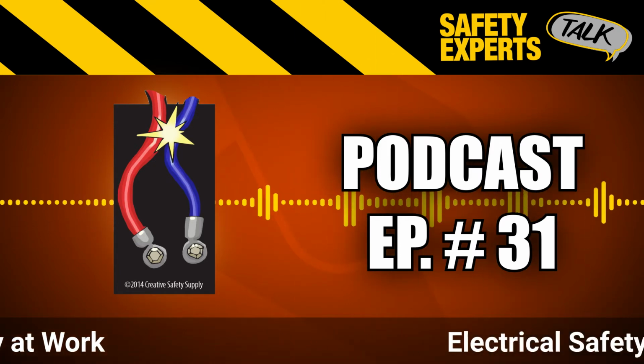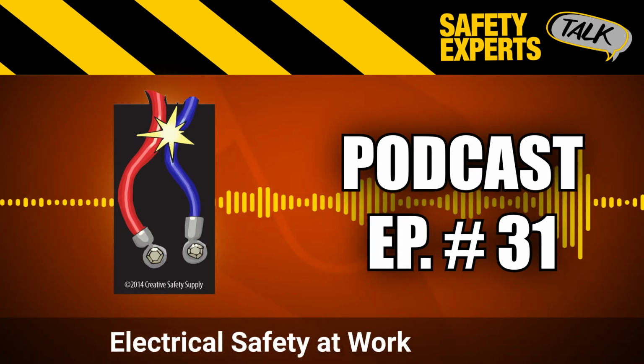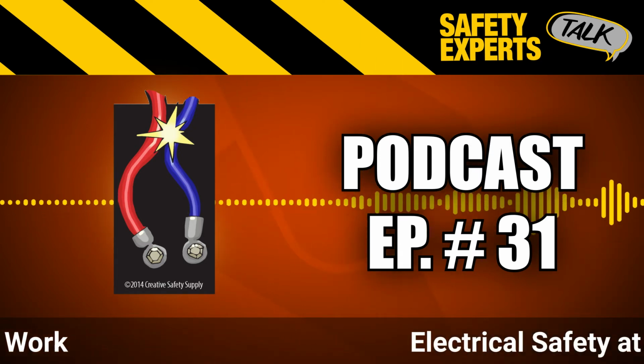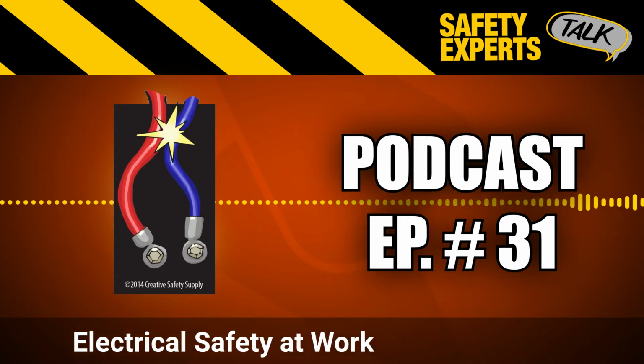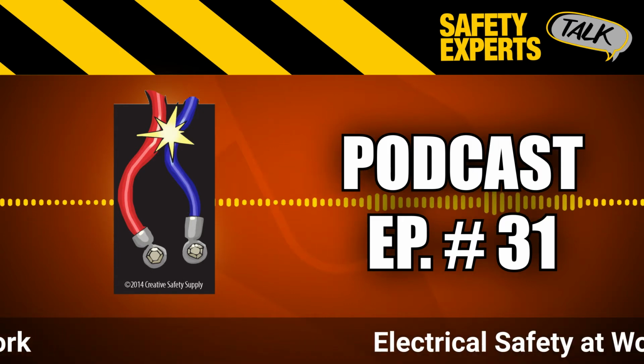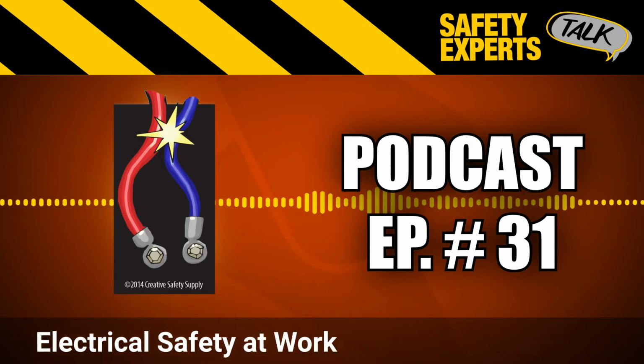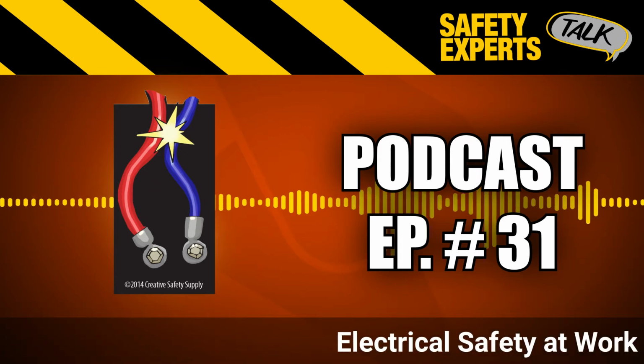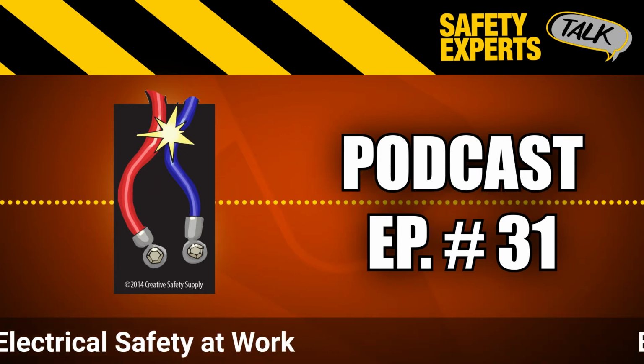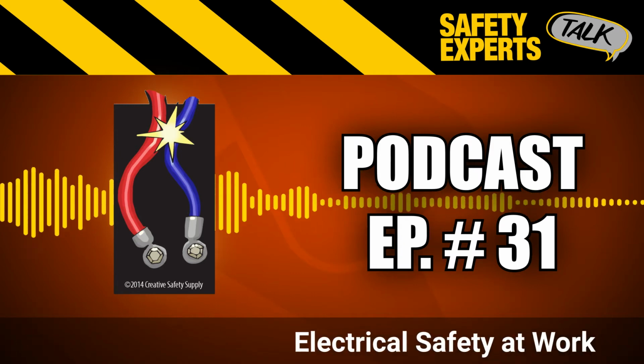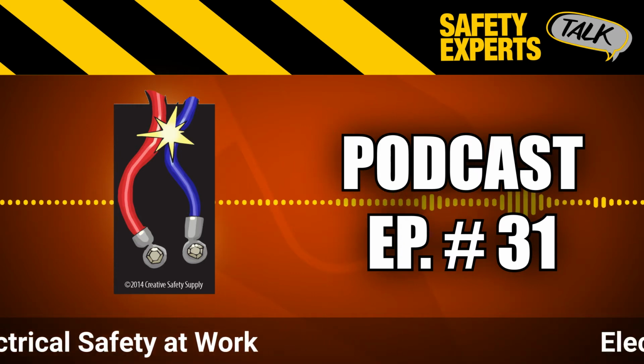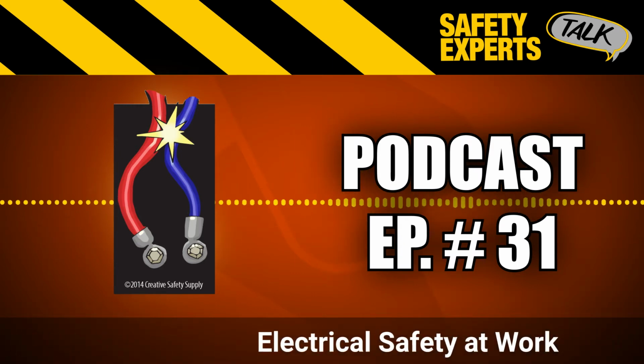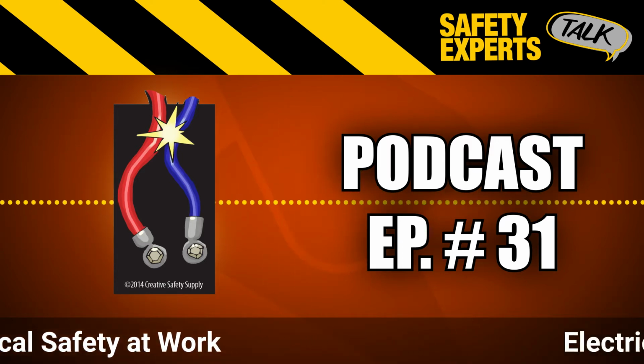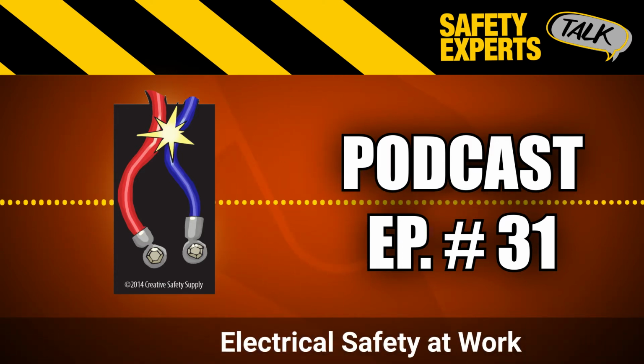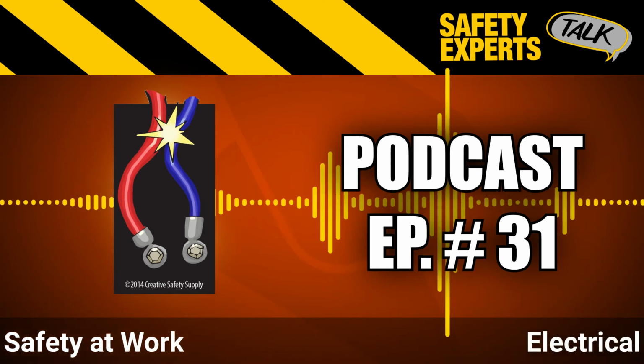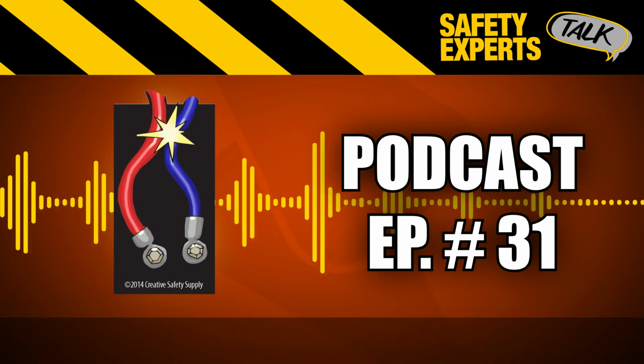Correct. And so people have to be very careful, and I think it's really important that you mentioned having somebody verify that the circuit is dead, because the electrician is going to verify not only the capacitor, which stores energy, but any accidental re-energization, a backfeed if a line were to touch another line, the backfeed into the system. So this electrician, or as we call it, the qualified person, is going to check for this stuff to ensure that it is properly de-energized and ready to work on.